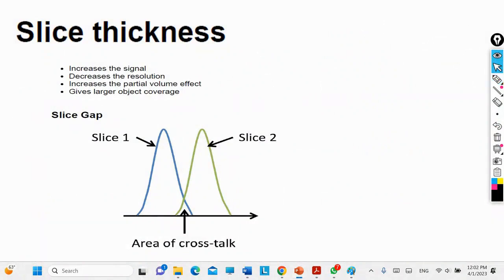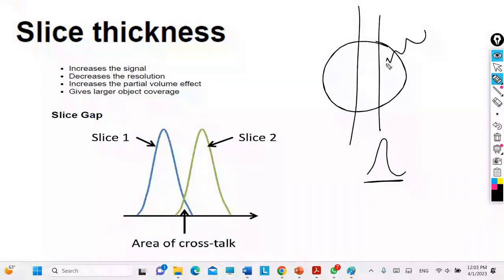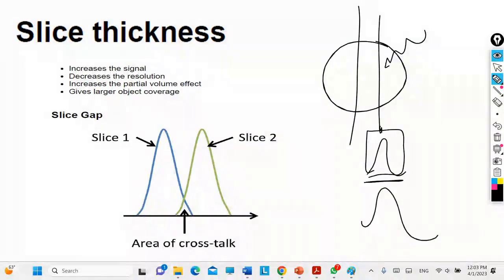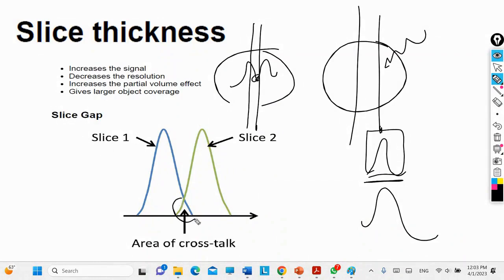Each slice has a profile — a specific shape. You don't just apply the RF pulse at one point; you take a window or range from the slice. There is a curve-like shape to your slice profile. If you have slices close to each other and take them sequentially, there is an overlap in the adjacent area, which is called crosstalk. This part has been affected by the first slice.